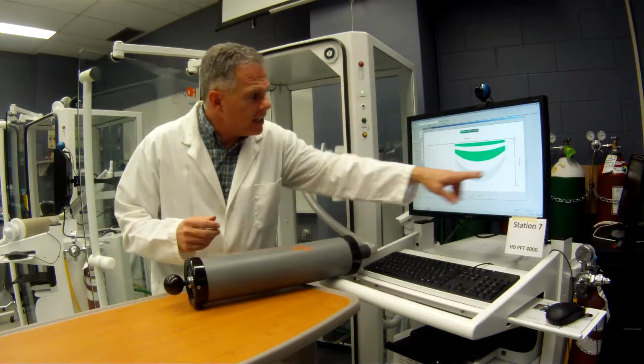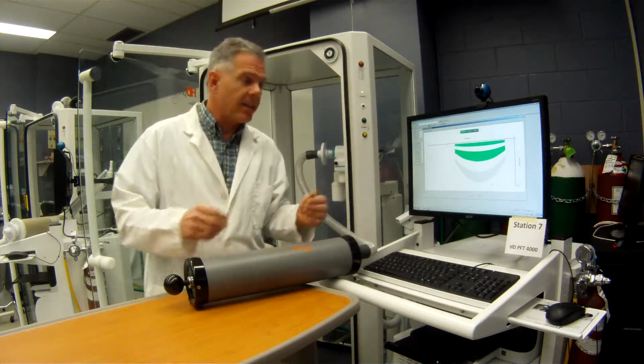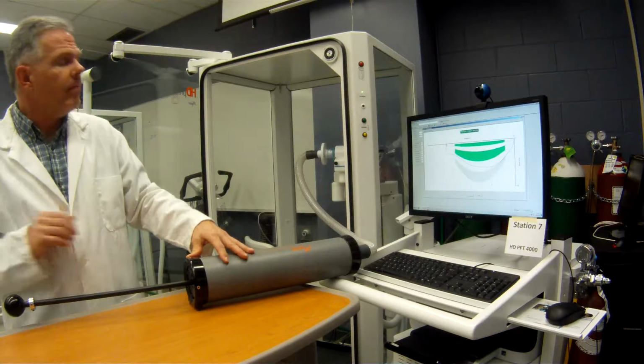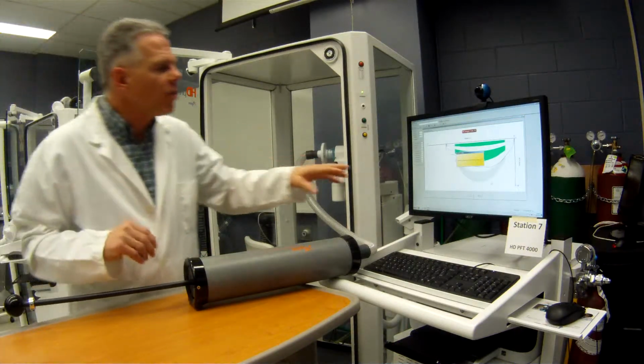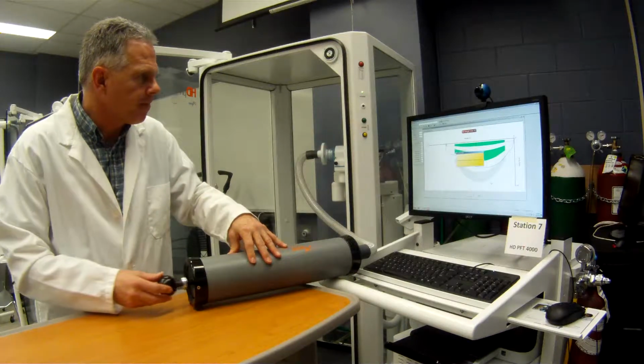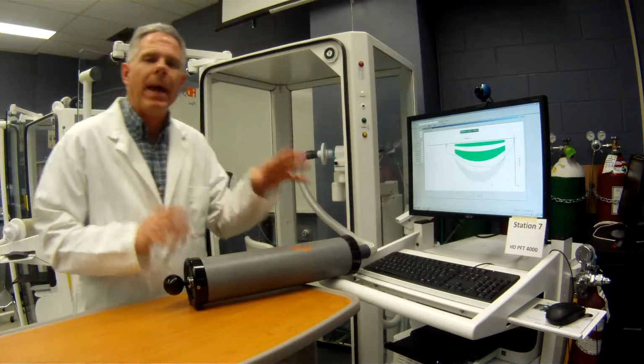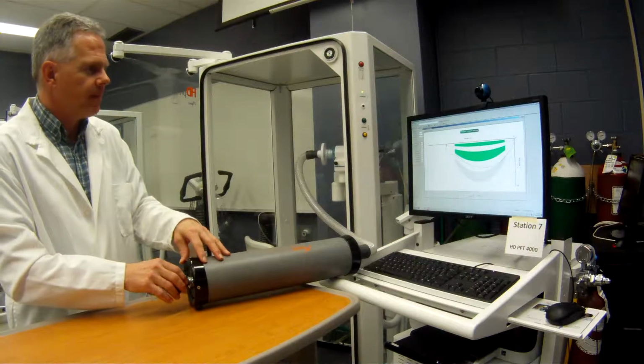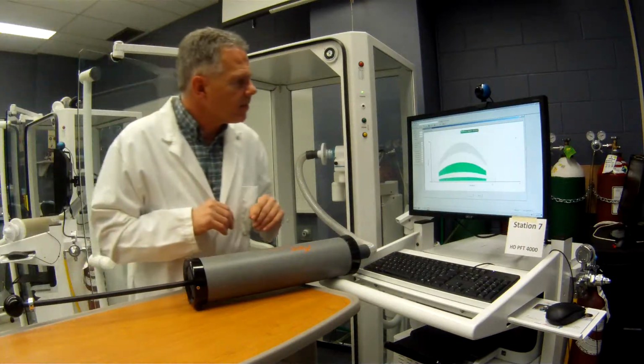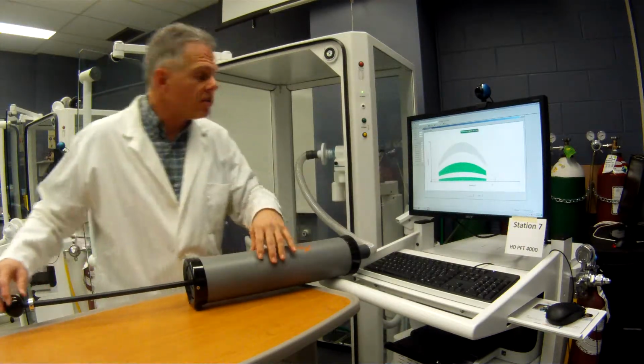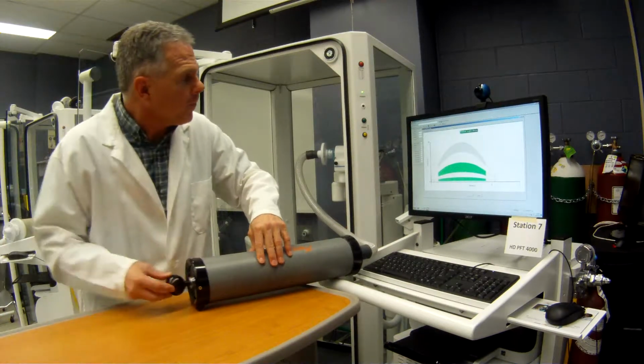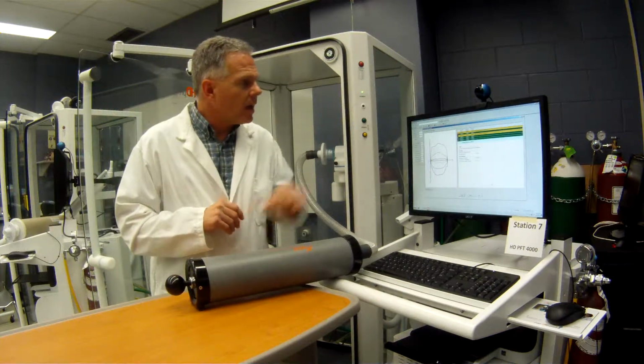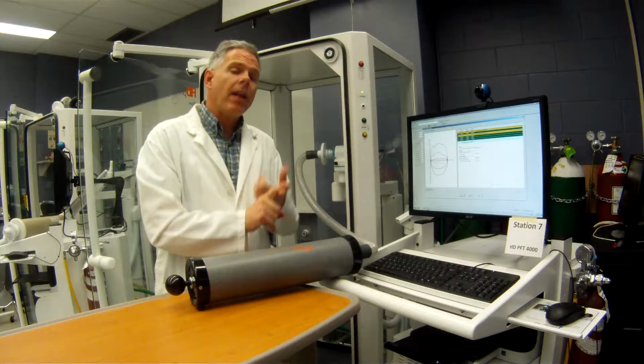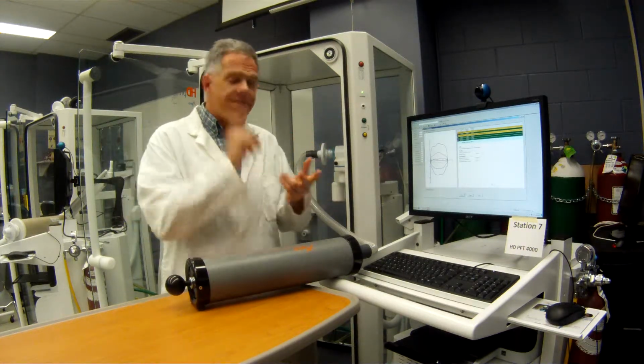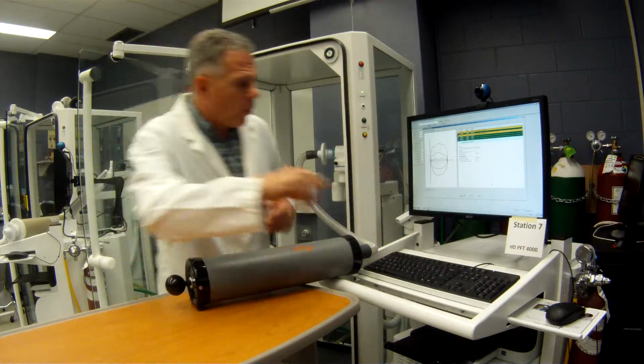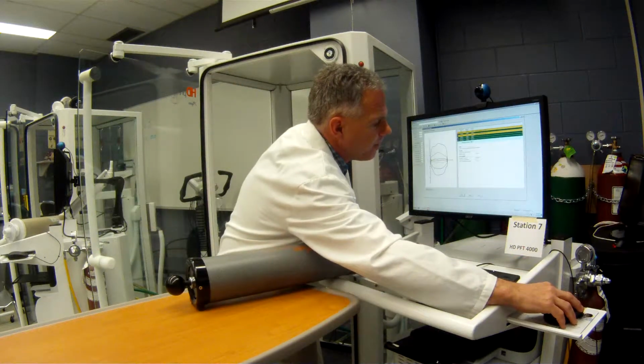So now we're doing the inspiratory stroke, and remember, we're just verifying at this point. All right. I find the inspiratory ones a little trickier because I don't like banging the syringe against the ends. Okay, so accepted that one. Now, just one last expiratory stroke. Okay, so now what we've done, we've calibrated our pneumotach. We verified that it's working correctly, so we can close this.